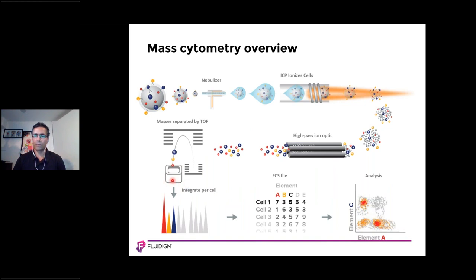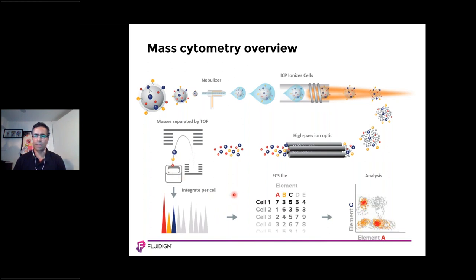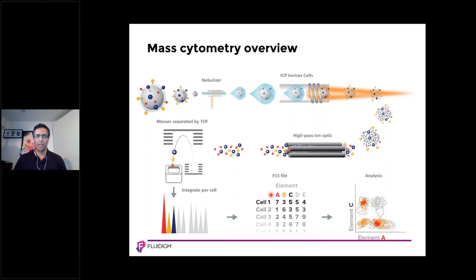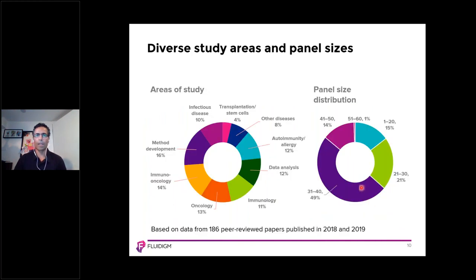One single detector in the instrument quantifies all the metal isotopes in the sample. In mass cytometry, this single detector needs to be calibrated, which minimizes day-to-day and site-to-site variation and generates more reproducible results, as I will discuss later in this presentation. Finally, the data matrix is converted into a conventional FCS file.